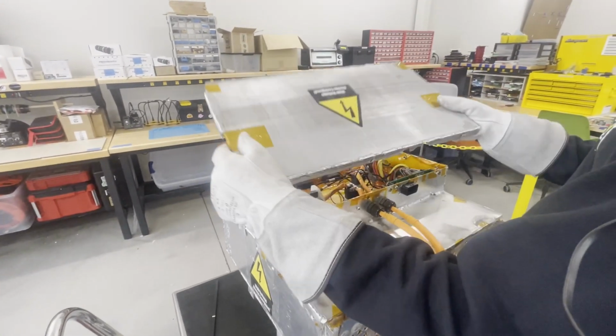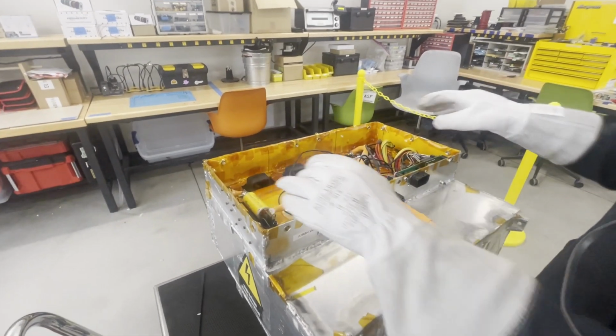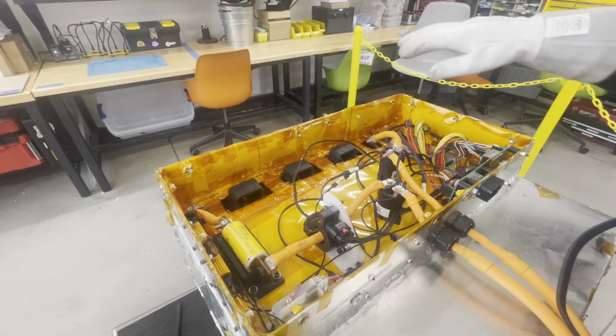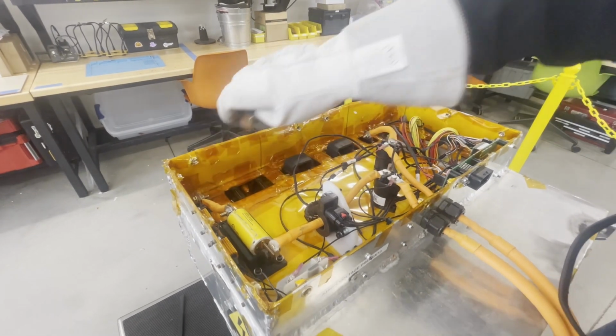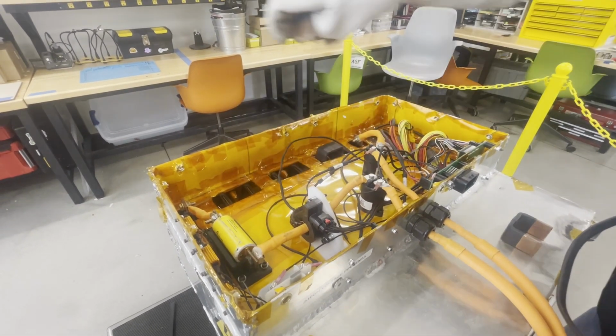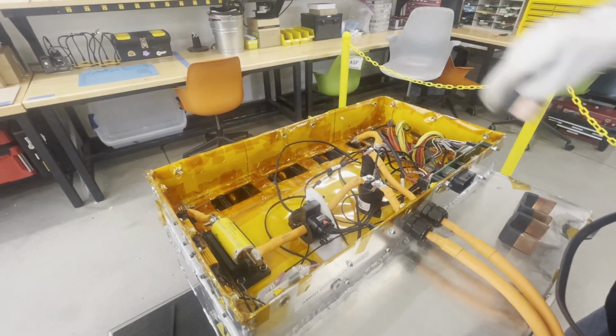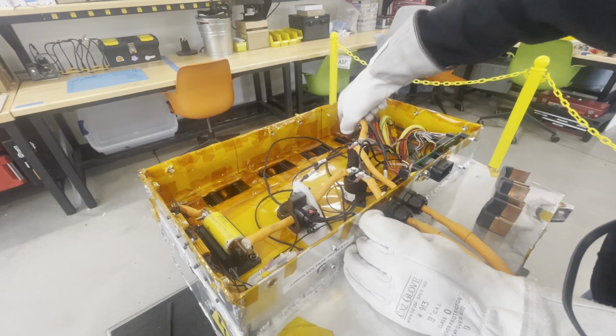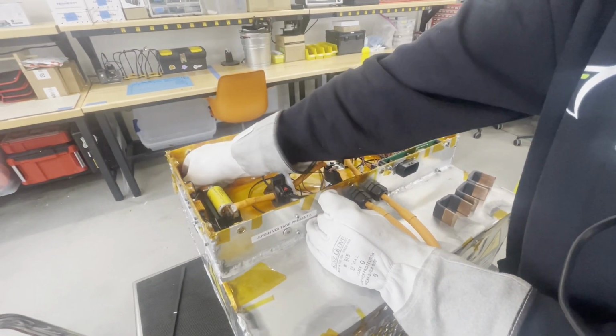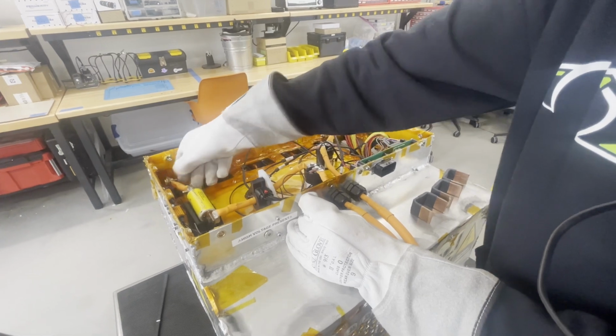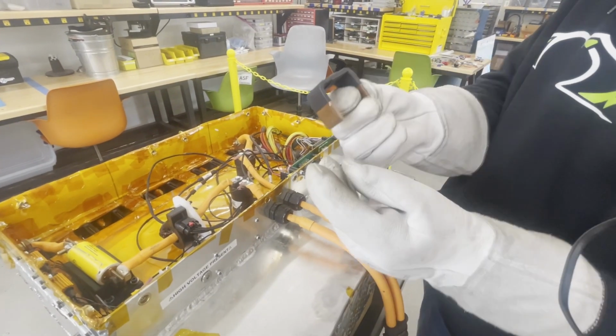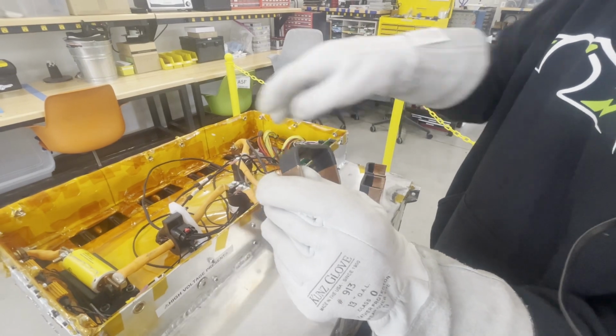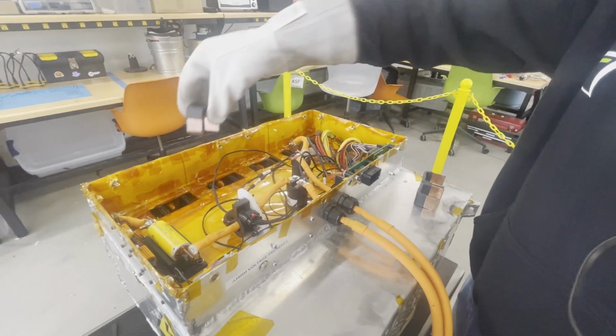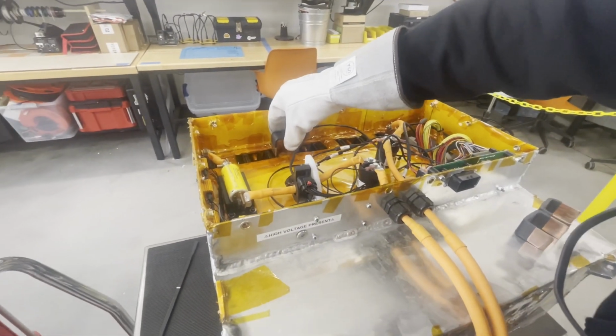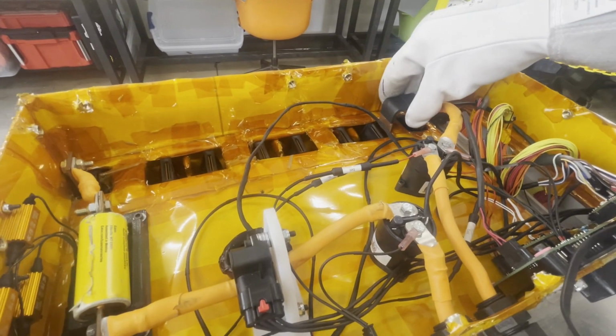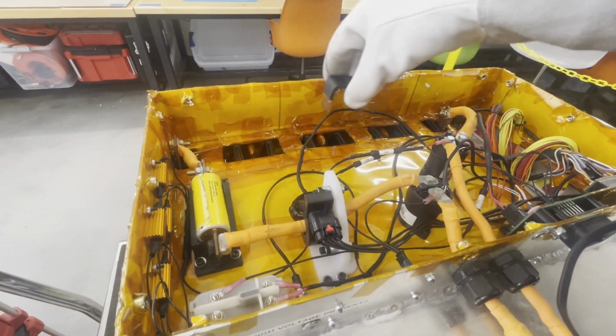Once we've unbolted the lid, take it off. The battery is fully connected and energized right now. Before any other wiring is touched, we can remove each of the service connectors without any additional tools to step the battery voltage down into 4 sets of 84 volts instead of the total 336. Once we have that, you can see that each of these bus bars is non-conductive where they stick out of the connectors, and then also it cannot be installed incorrectly to short any of the modules together in an improper fashion, and obviously these can't reach across.